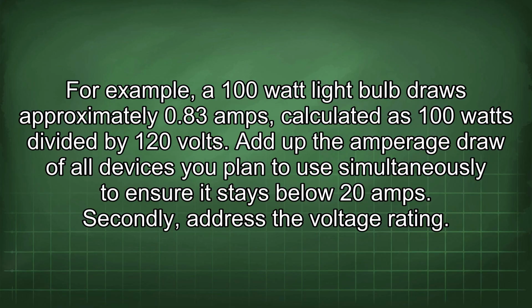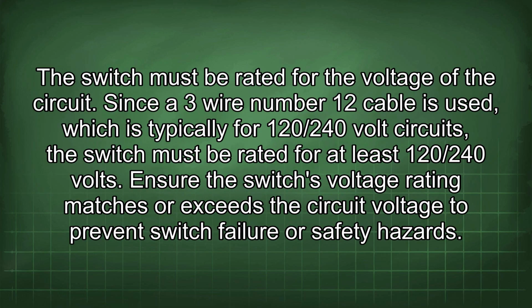Secondly, address the voltage rating. The switch must be rated for the voltage of the circuit. Since a 3-wire number 12 cable is used, which is typically for 120/240 volt circuits, the switch must be rated for at least 120/240 volts. Ensure the switch's voltage rating matches or exceeds the circuit voltage to prevent switch failure or safety hazards.